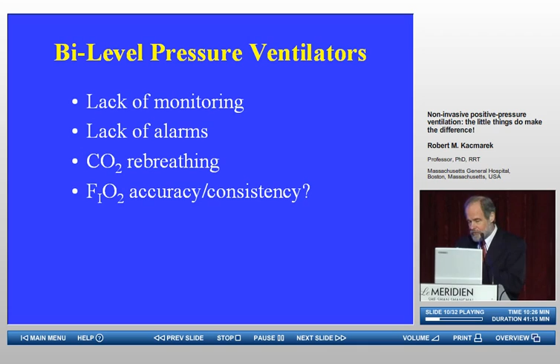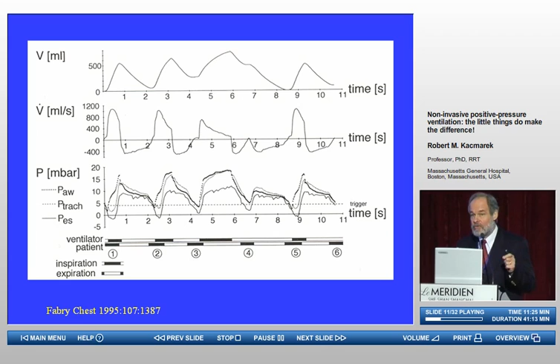But one of the big disadvantages is that in most of these ventilators, you cannot see waveforms on the patient during non-invasive ventilation. Now, this is a patient intubated receiving pressure support ventilation, and as you can observe, a tremendous amount of dysynchrony. Well, the same level of dysynchrony can exist with patients receiving non-invasive ventilatory support. Now, without some visual feedback on how well we're delivering that non-invasive ventilation, we can make some assumptions that simply are not consistent with the reality of the way that patient is actually being ventilated.